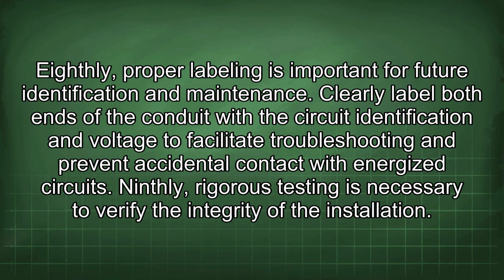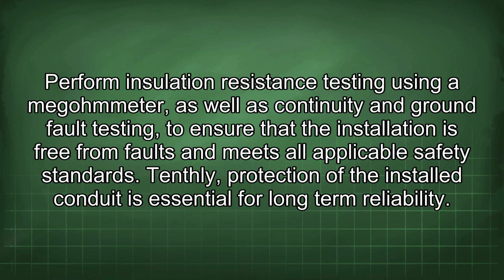Eighthly, proper labeling is important for future identification and maintenance. Clearly label both ends of the conduit with a circuit identification and voltage to facilitate troubleshooting and prevent accidental contact with energized circuits. Ninthly, rigorous testing is necessary to verify the integrity of the installation. Perform insulation resistance testing using a megohmmeter, as well as continuity and ground fault testing, to ensure that the installation is free from faults and meets all applicable safety standards.